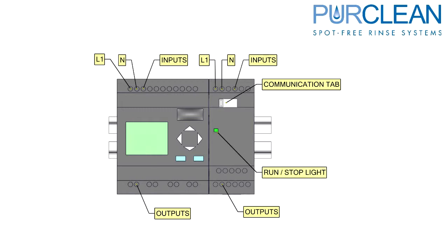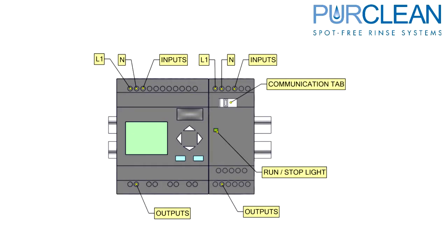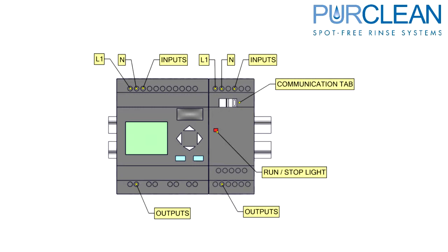The Run Stop light will be green when there is power supplied and the communication tab is pushed to the left. If the communication tab is pushed to the right, the light will be red indicating power is present, but there is no communication.